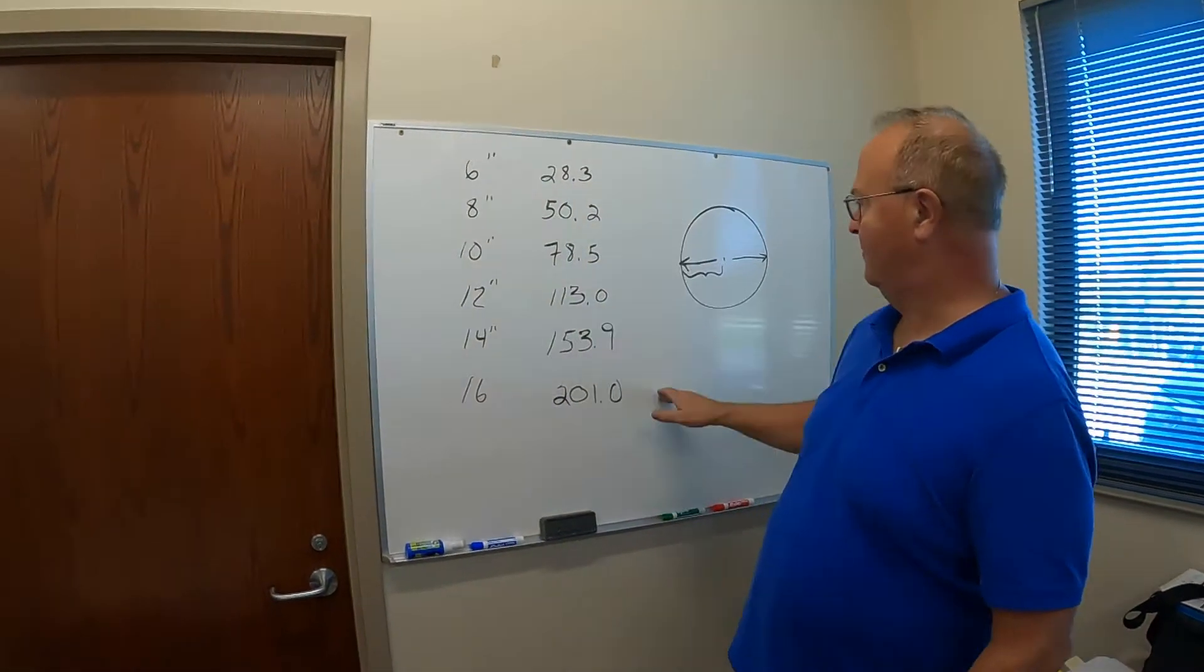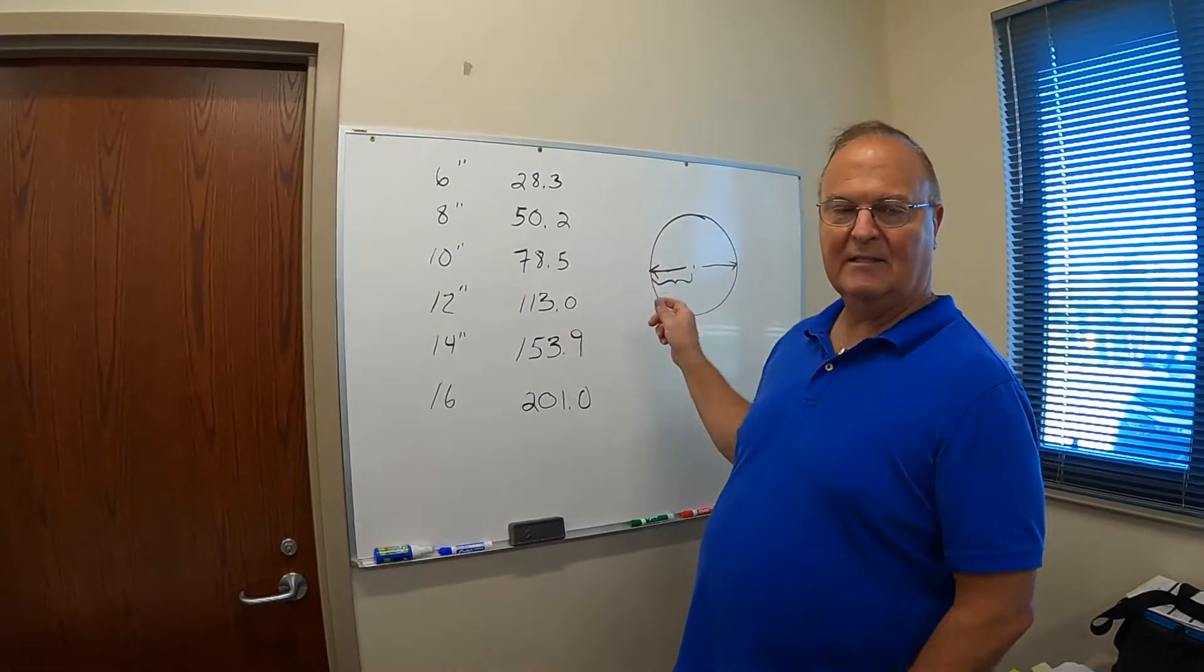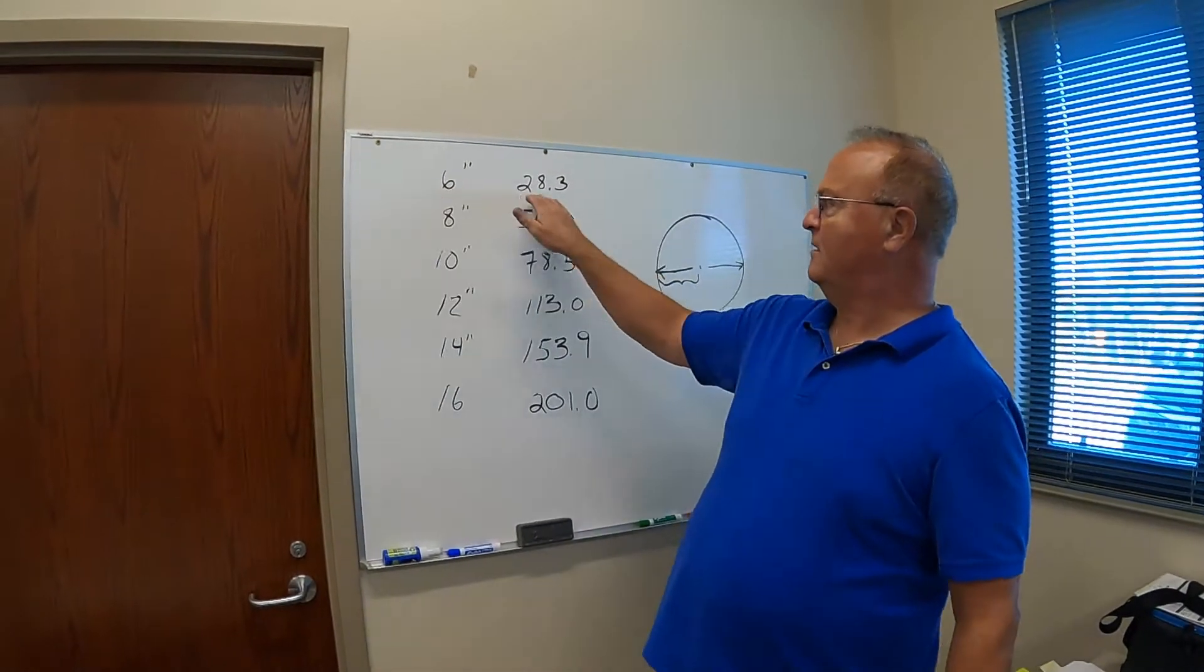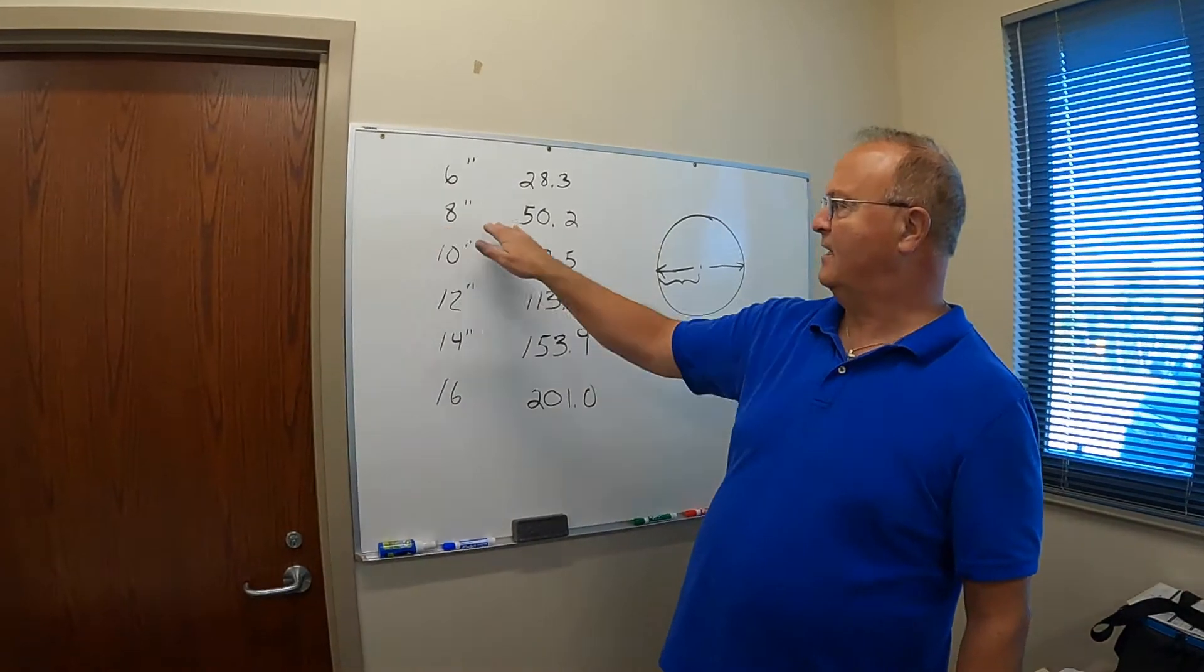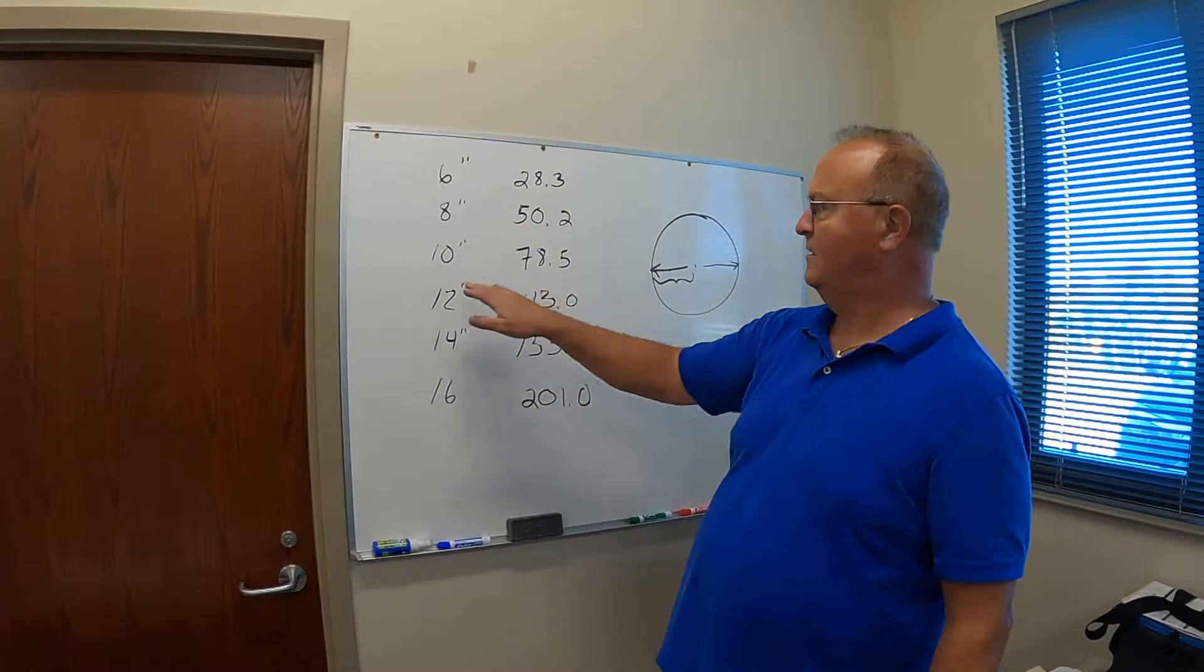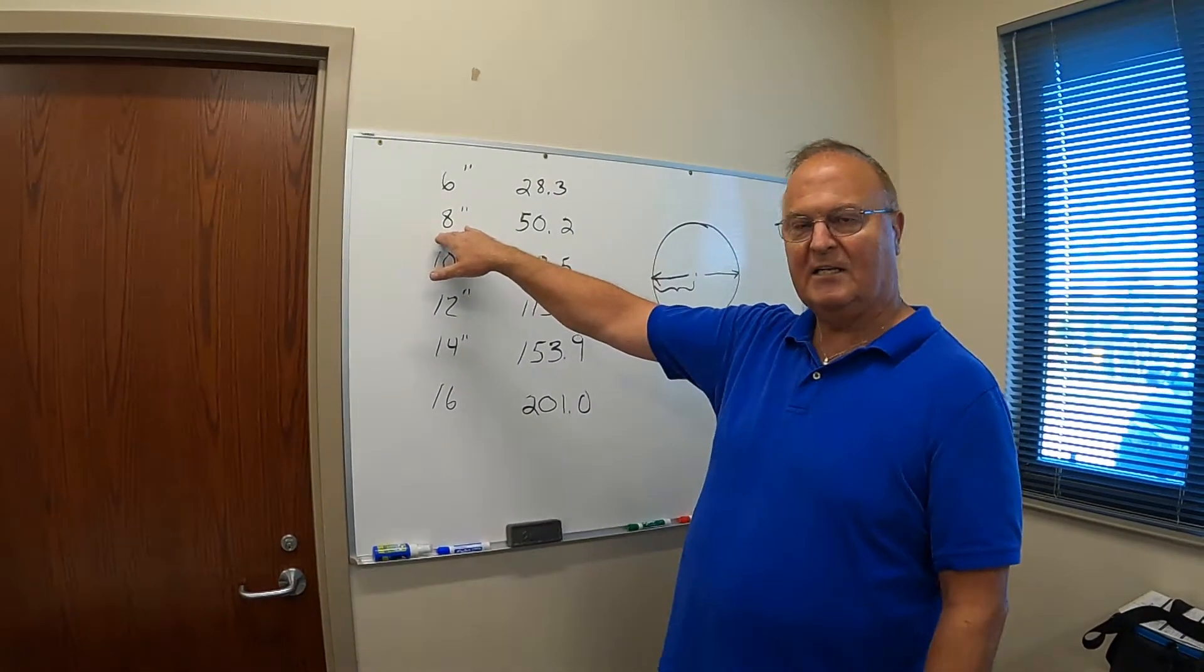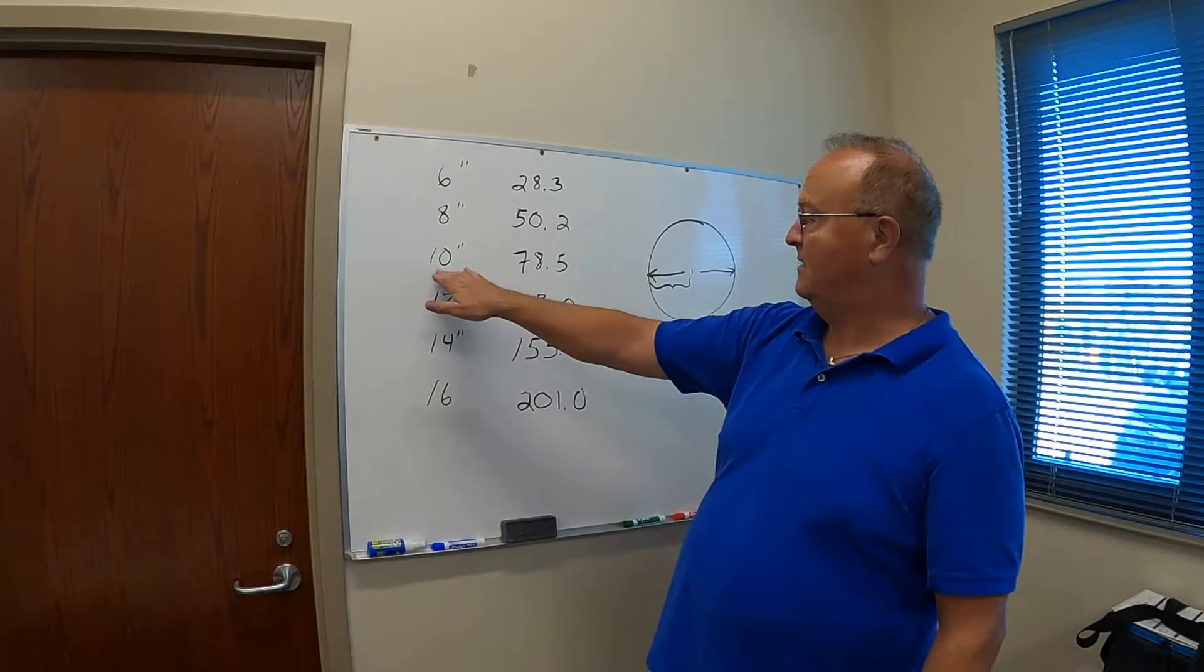So you would take the radius, and you'd square it, and you'd take it times pi, 3.14. So a 6 inch round duct is 28.3 square inches, an 8 inch round duct is 50 square inches. So if you want, you could run four 8 inch ducts, and you'd have between 180 and 200 square inches.